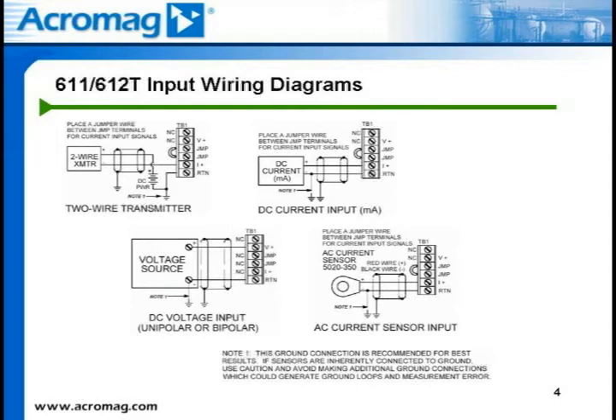And finally, the last schematic shows how to monitor AC current using Acromag's toroid sensor. This toroid produces a sourced DC current that can be wired to the 611T or 612T input terminals as shown. This enables transmitting the value of the AC current over long distances for monitoring and control applications. And this sensor provides accurate and safe monitoring of AC loops, as the secondary side of the Acromag toroid includes built-in diodes, so the output loop may be opened without causing harm to the live primary AC current loop.